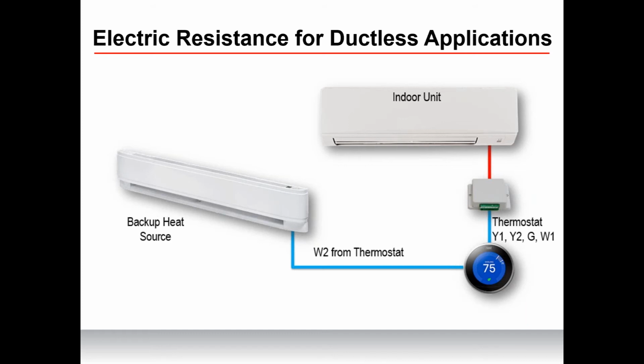It's as simple as that. So it'll only engage if the space temperature drops to this temp. You can do that. That's a simple application. However, that's okay if you're leaving it as just an emergency backup type thing. That may not be necessarily a good comfort strategy from a controls application to actually engage that backup heat.